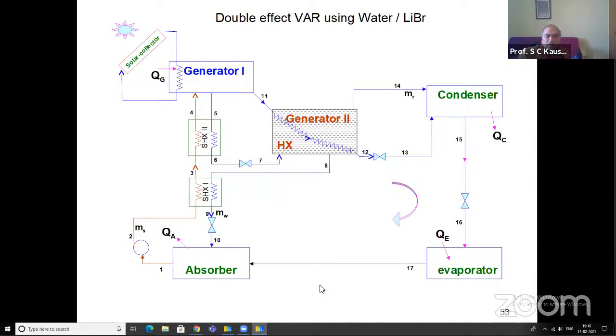What is a double effect generation vapor absorption system? Between the generator and the condenser, we provide an additional heat exchanger. The solution left behind in the generator is reduced in temperature as well as in pressure, and then it is sent to this heat exchanger, where the vapor generated from generator one is being condensed. So that heat of condensation is available for heating the solution in generator two, and thereby more refrigerant vapor can be generated at this stage.